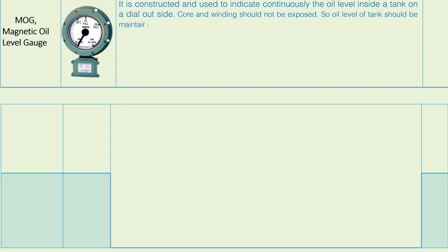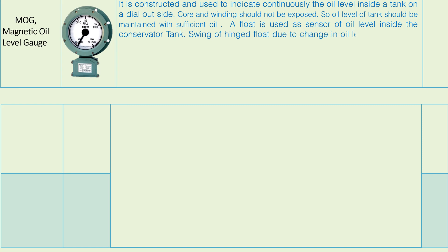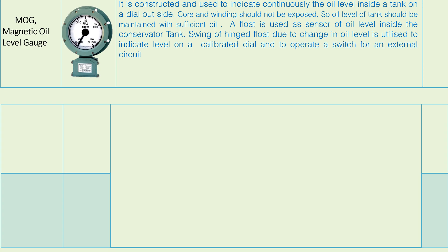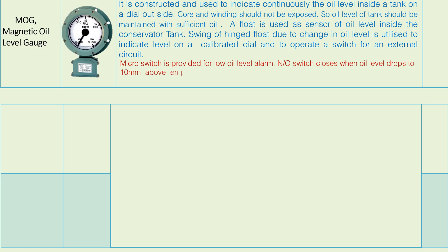MOG — Magnetic Oil Level Gauge: It is constructed and used to continuously indicate the oil level inside the tank on a dial outside. Core and winding should not be exposed, so the oil level of the tank should be maintained with sufficient oil. A float is used as a sensor of oil level inside the conservator tank. The swing of the hinged float due to change in oil level is utilized to indicate level on a calibrated dial and to operate a switch for an external circuit. A micro switch is provided for low oil level alarm; the switch closes when oil level drops to 10 mm above empty, that is 75 mm from the bottom of the conservator. The indicator can be mounted in a tilted position toward ground, maximum 30 degrees, for easy viewing.